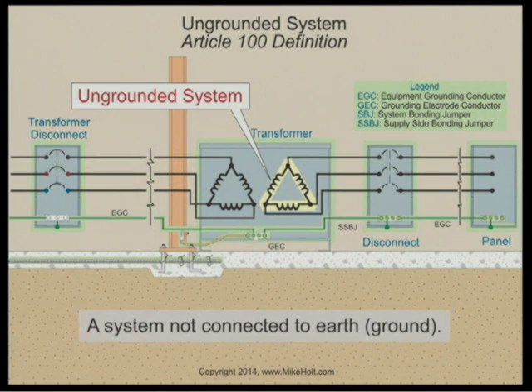Eric? Well, let's just say this were already installed and you decided to ground it, and you already were in a fuse disconnect. Hold on. Let's go with this example, the graphic you're saying here. So I just want to bring up the picture you're talking about. Okay. You're saying we have this, everything is great. This is black, red, whatever colors, and then a breaker, simultaneous. A simultaneous breaker is fine, but now let's say that disconnect is fuses, 3 individual fuses. Okay, now if that's 3 individual fuses, and you ground that bottom left corner of the delta and follow that line over to the fuse holder, you would replace that fuse with a slug or a bar.